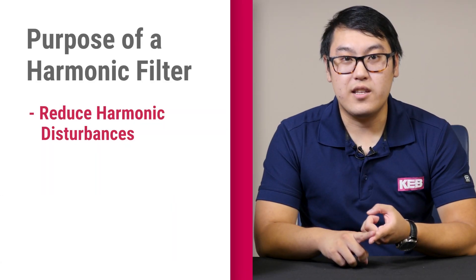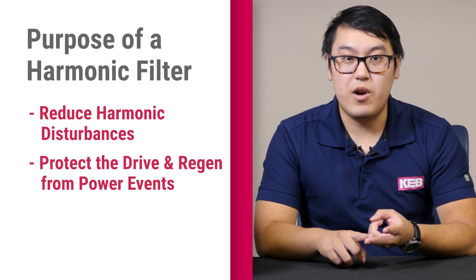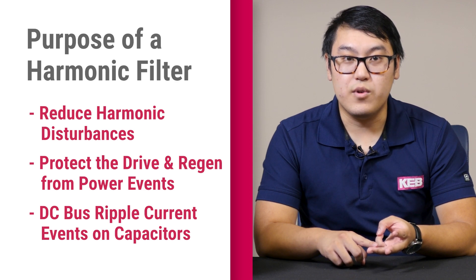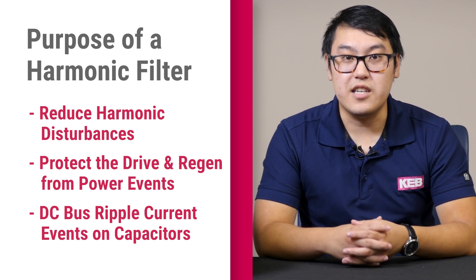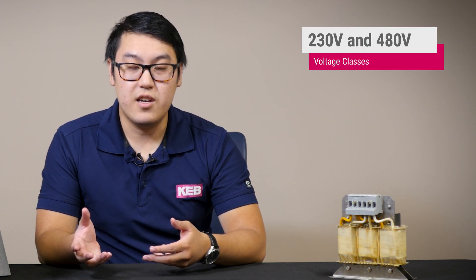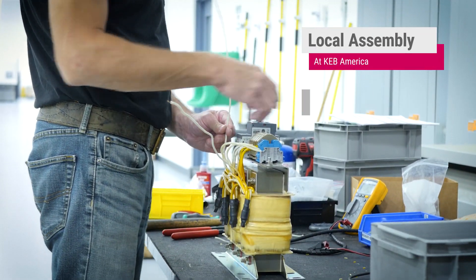What's the purpose of having a harmonic filter? It's to reduce harmonic disturbances, protect the drive and regen from power events such as a brownout, and to reduce the DC bus ripple current effects seen on the DC bus capacitors. The KEB harmonic filters are offered in both 230 and 480 voltage classes. They are all UL certified and assembled here at KEB America.